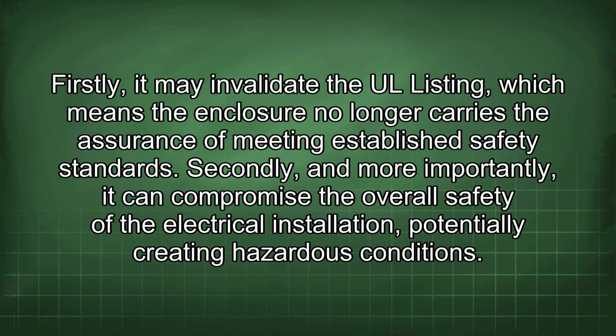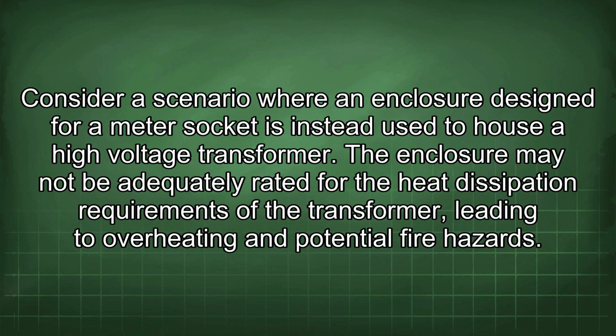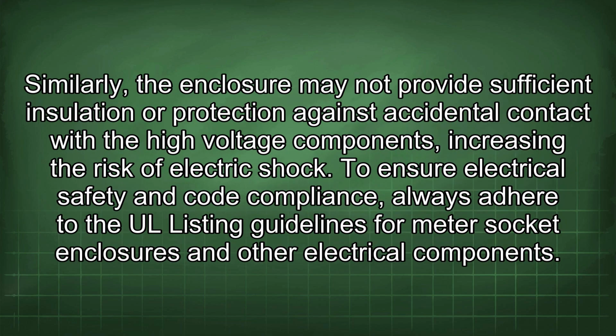Firstly, it may invalidate the UL listing, which means the enclosure no longer carries the assurance of meeting established safety standards. Secondly, and more importantly, it can compromise the overall safety of the electrical installation, potentially creating hazardous conditions. Consider a scenario where an enclosure designed for a meter socket is instead used to house a high-voltage transformer. The enclosure may not be adequately rated for the heat dissipation requirements of the transformer, leading to overheating and potential fire hazards. Similarly, the enclosure may not provide sufficient insulation or protection against accidental contact with the high-voltage components, increasing the risk of electric shock.